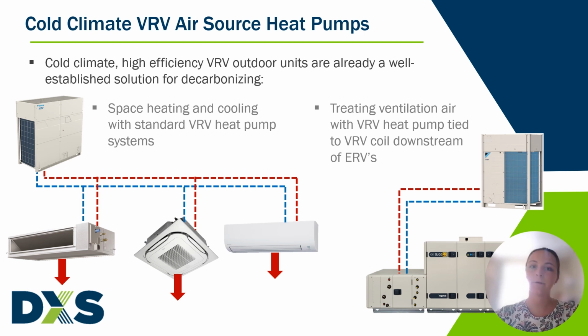So VRV has already been around for years, and at this point is a well-known and well-trusted solution in the industry, and has already been very effective and utilized often for decarbonization efforts. And VRV is a solution for electrifying and decarbonizing space heating and cooling, and we would do that through the use of our standard VRV heat pump or heat recovery systems, which would be tied to standard VRV indoor units. And you can see an example of that on the left side of the screen. And not only that, but we also use VRV to decarbonize treating our ventilation air by tying a VRV heat pump to a VRV coil downstream of an ERV. Or we could do a similar setup to decarbonize air handling units.